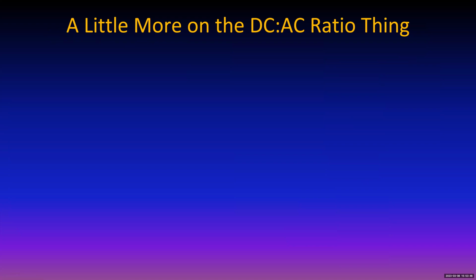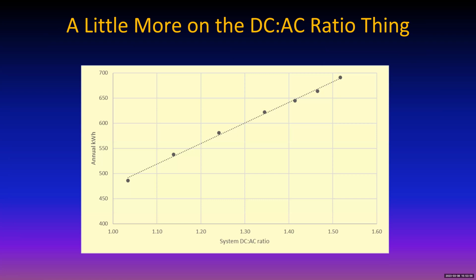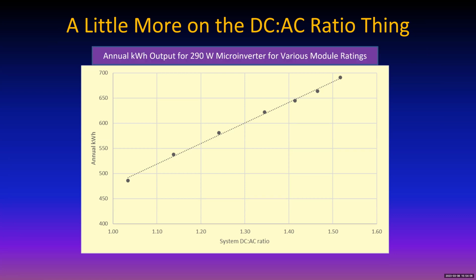Okay, I've been talking about DC to AC ratios. In other words, the size of the array in watts is a whole lot bigger than the rating of the inverter in watts. And let's see what the losses are. I did some simulations with the 290 watt microinverter with a number of different modules. And here's what we get in terms of kilowatt hours annual output for a 290 watt microinverter, depending on the size of the module connected to it.